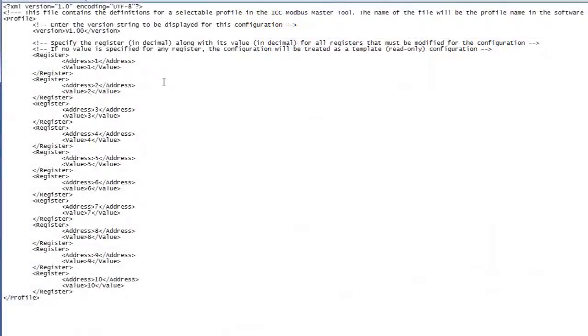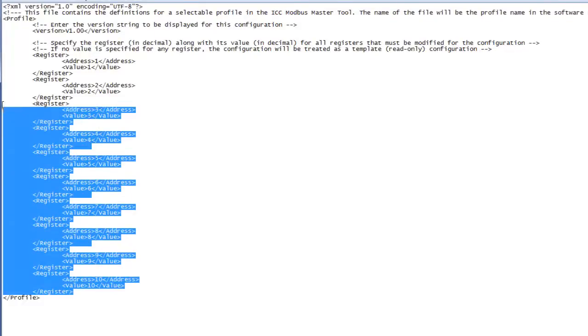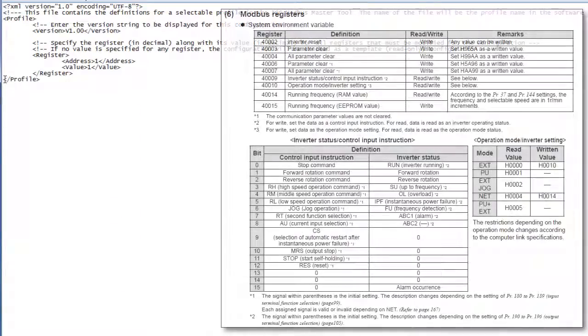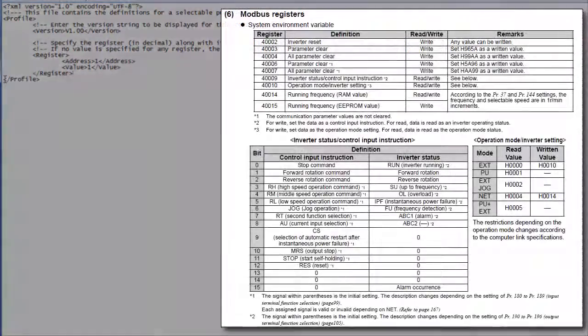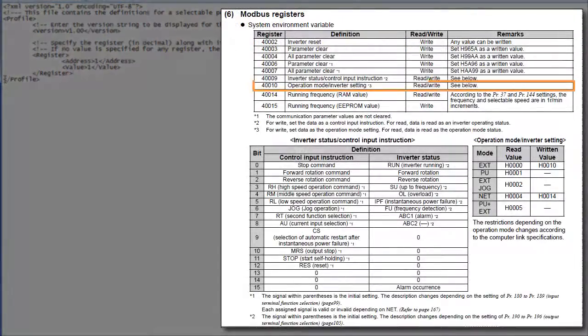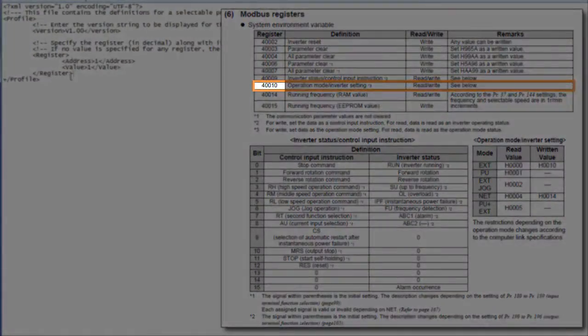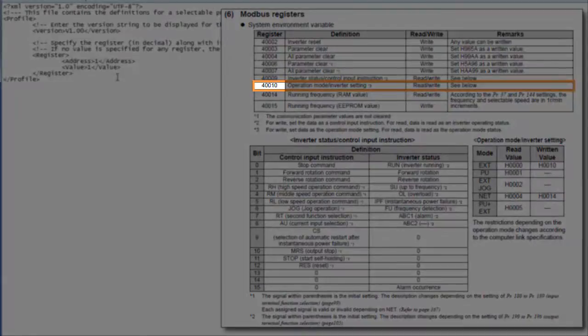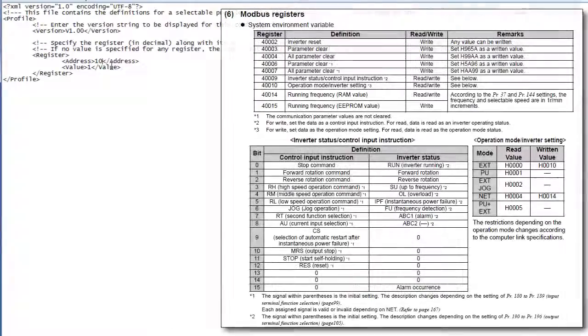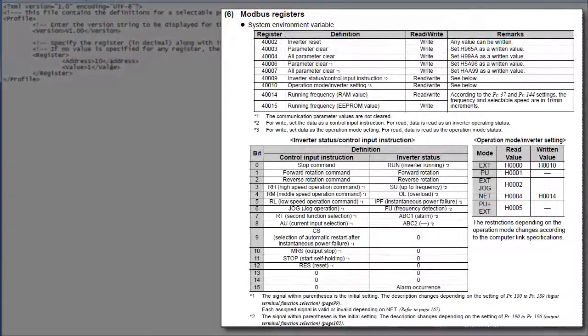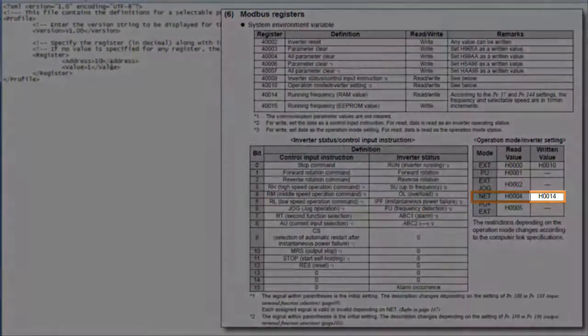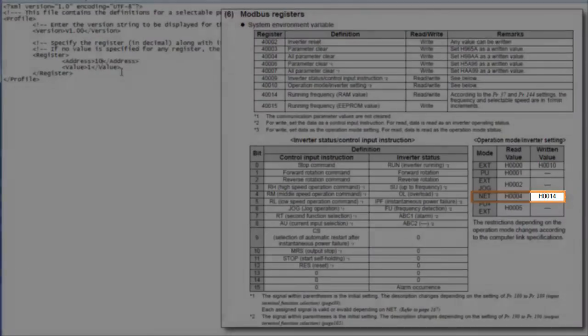Let's start by removing all but one of the register entries in our file. The first parameter we need to set is the operation mode. The register for it is 40,010, which means holding register 10. So we'll enter 10 for our first register's address. The value to set the operation mode to network is 14 in hex, which is 20 in decimal. We'll enter 20 for the register's value.